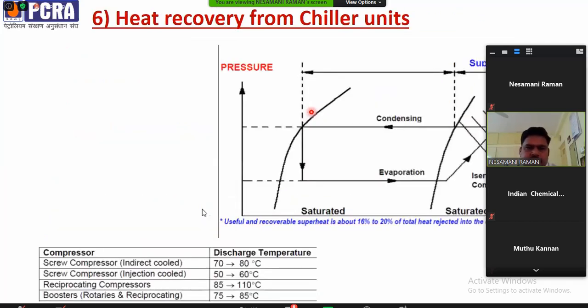So the sixth point is heat recovery from chillers. If you see the chiller or HVAC refrigerant flow diagram, pressure is on the vertical axis and enthalpy is on the horizontal axis. Evaporation takes place at constant low pressure; the liquid refrigerant after condensation enters here at low pressure and gets vaporized. Here we install a cooling coil, where chilled water enters, gives away its heat to the refrigerant, gets chilled, and goes to the process or HVAC system, the AHU.